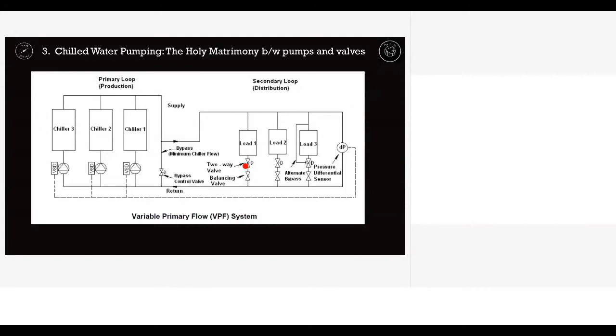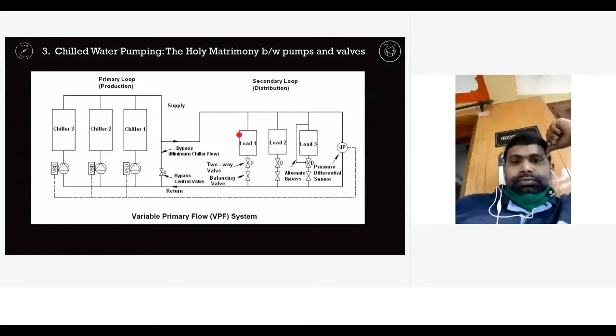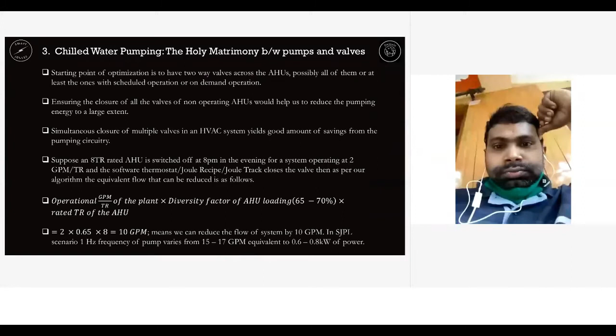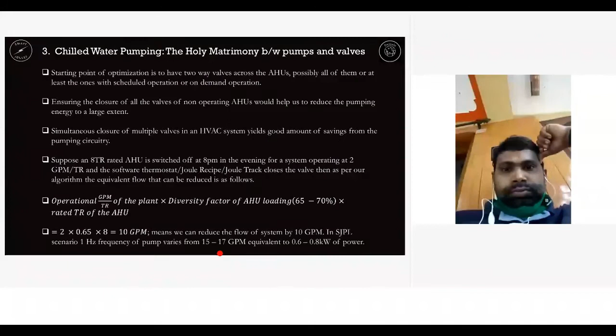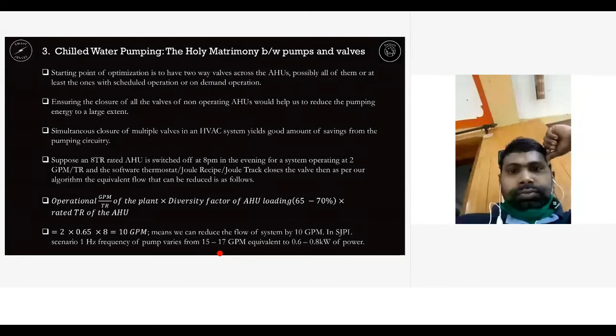The more two-way valves you have, the more you can exploit the shutdown nature of the loads, that is, the heat exchangers in the building. If you don't have this valve, and if these are not integrated to IoT and BMS, then even though we know that this is off, we can't shut it down. So everything needs to be connected into a single platform. I'm moving forward because of the lack of time. This is again the calculation. All the things that I've just told are written down here. You can read it as I say, but the point is, the more valves, the better it is for the building.